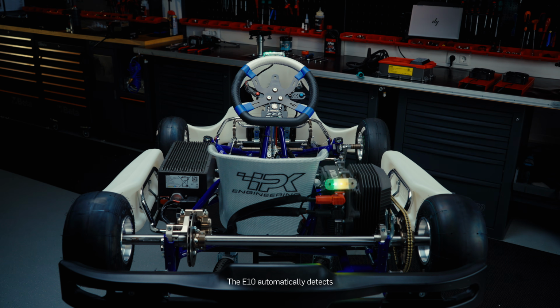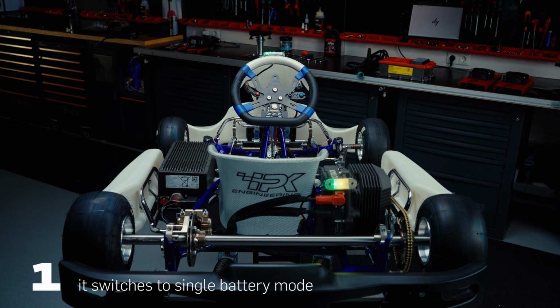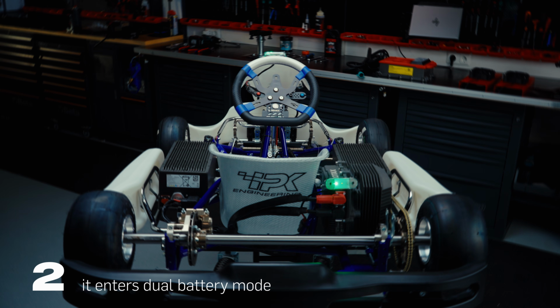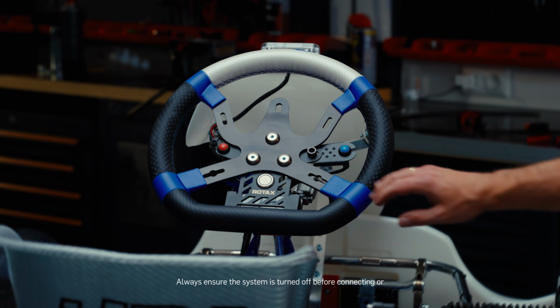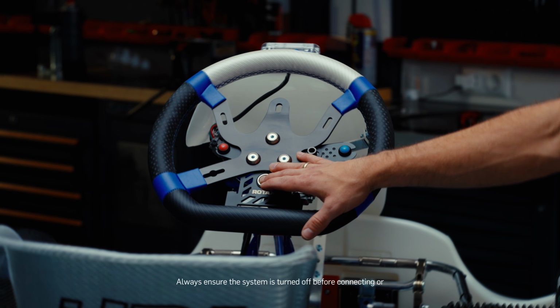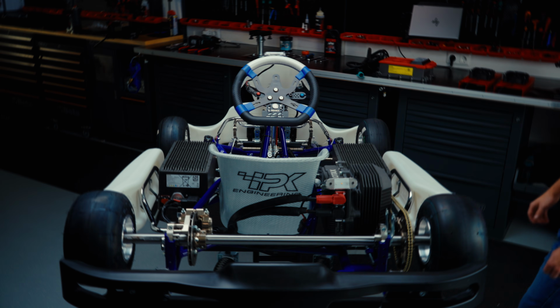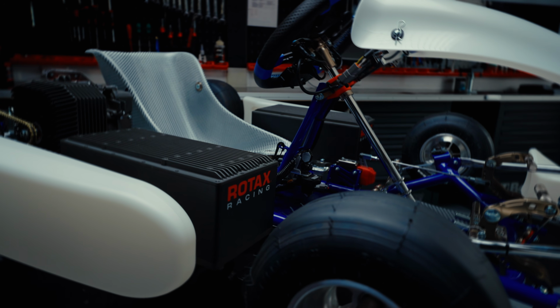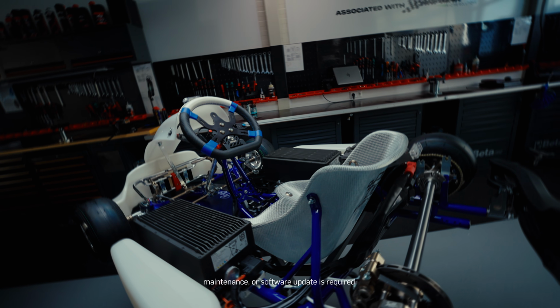The E10 automatically detects how many batteries are connected. With 1 battery, it switches to single battery mode. With 2, it enters dual battery mode. Always ensure the system is turned off before connecting or disconnecting a second battery. No additional service, maintenance, or software update is required.